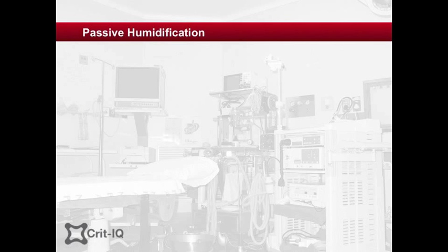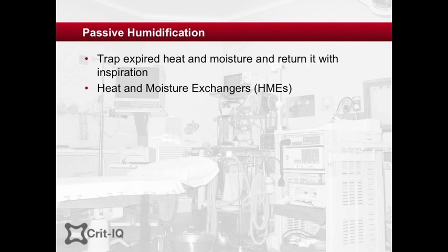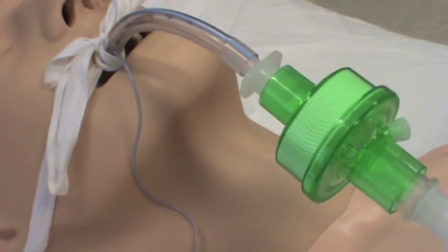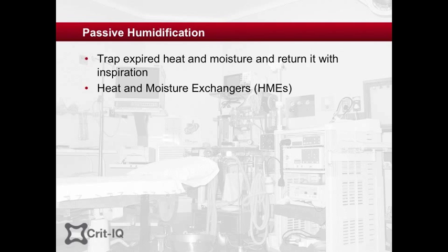Passive methods involve the insertion of a specialised filter that traps heat and moisture from the exhaled breath and returns it to the inhaled air mixture as it passes through the filter. These devices are known as heat and moisture exchangers, or HMEs. These have been designed to fit into the circuit as shown here, or for use on a tracheostomy tube in a spontaneously ventilating patient. The latter is known as a Swedish nose.